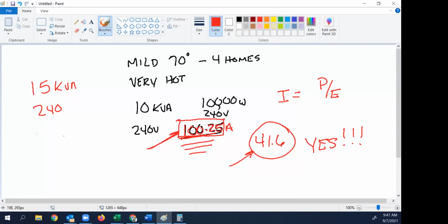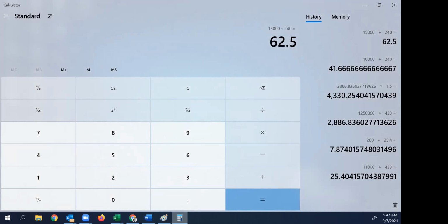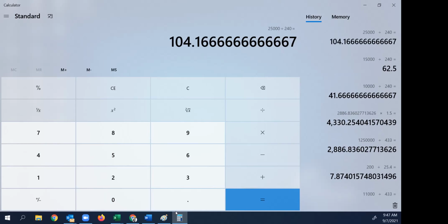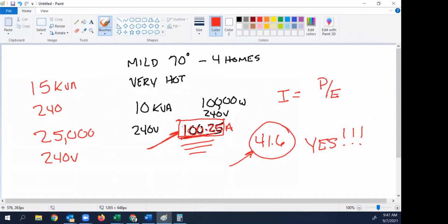So let's try 25 kVA, with a secondary voltage of 240. That's 25,000 watts. Let's punch that into the calculator. Clear this entry. 25,000 divided by 240 equals... bingo, 104.1. Nice, that covers the 100.25. That 25 kVA will fit nicely.